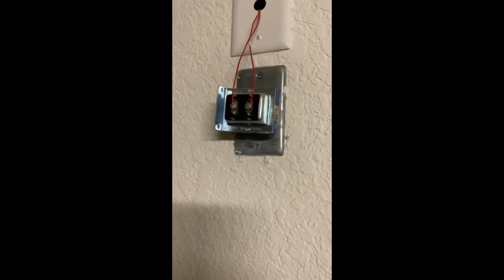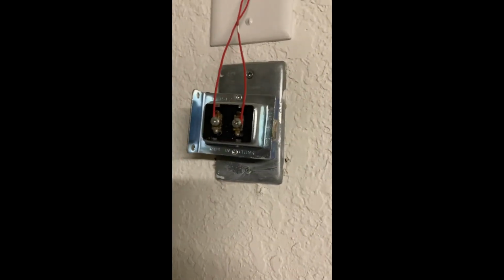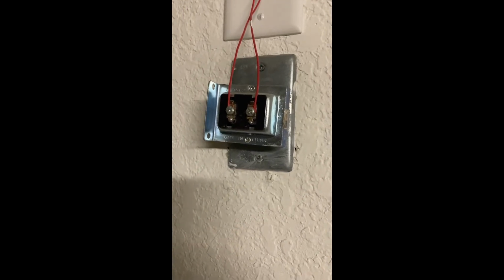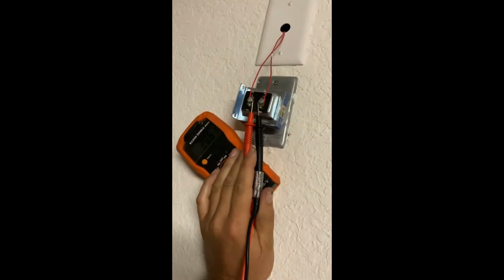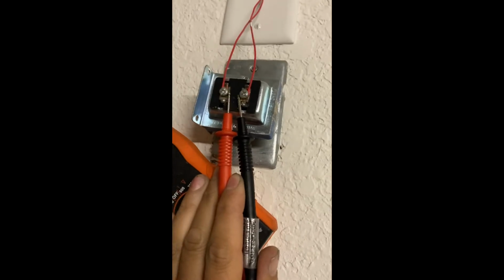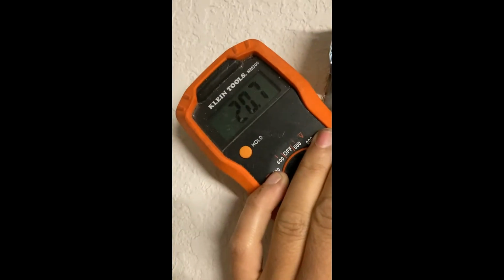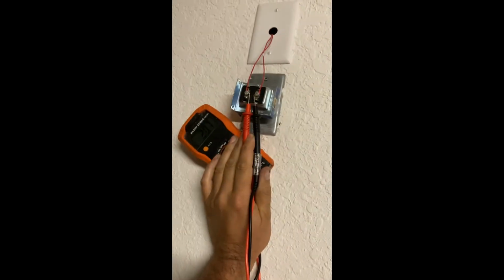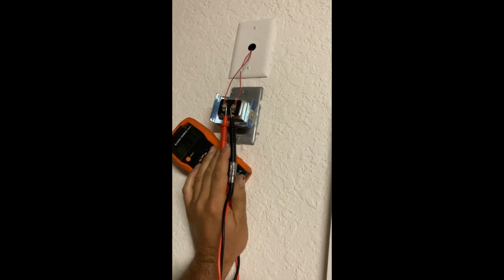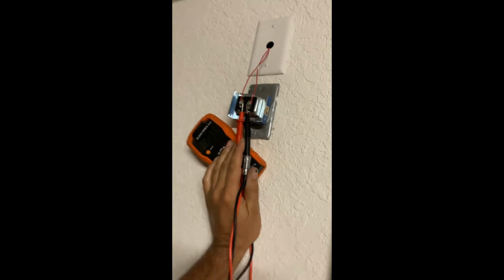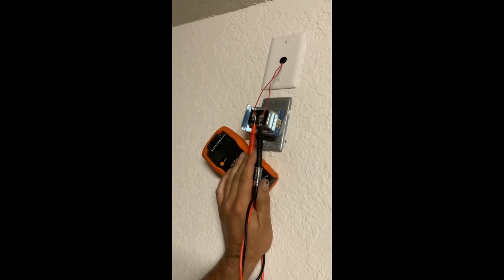So you want to start with your transformer and put your voltage meter there to confirm you have 16 volts. I have my leads on each terminal and I'm reading 20 volts, so that's good — this transformer is fine. If I had no voltage here, that would be the problem and I'd have to replace it. So that one's good, let's keep going down the line and see what problems we find.